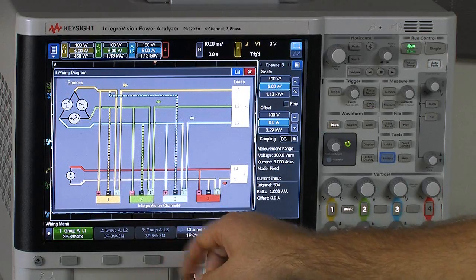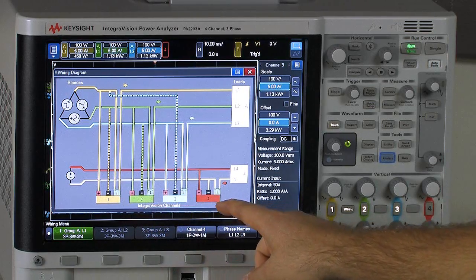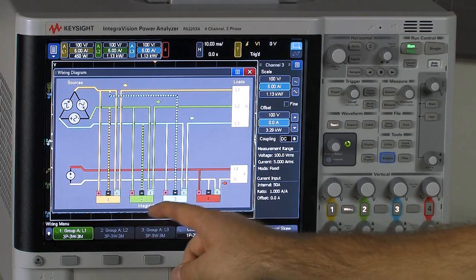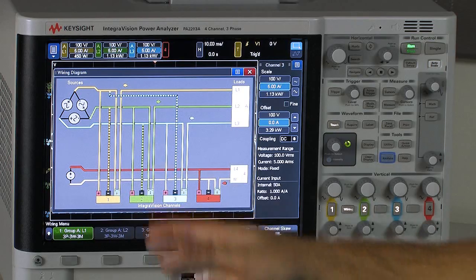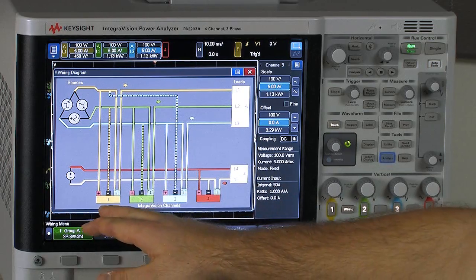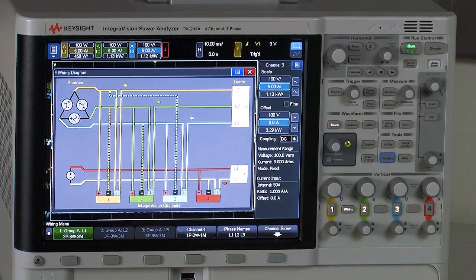The key thing to notice here is that the actual connections to the instrument are along the bottom of the screen. So I have channels one, two, three, and four on the rear panel of the instrument. And so basically the diagram is showing how do I connect up to my voltage and how do I connect up to the current inputs.